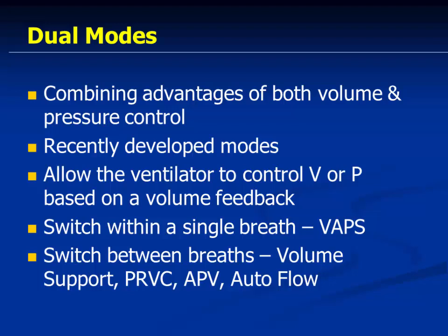Variable volume, and the benefit was flow was not limited. So the benefit of pressure control is that flow is not limited, and the benefit of volume control is that volume is guaranteed. So why can't we take the benefit of both the systems with a microprocessor and combine them? That's how it becomes a dual mode.